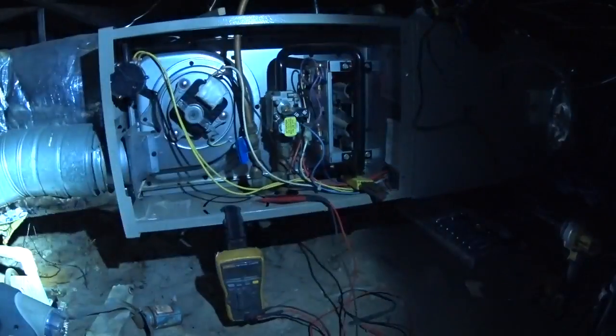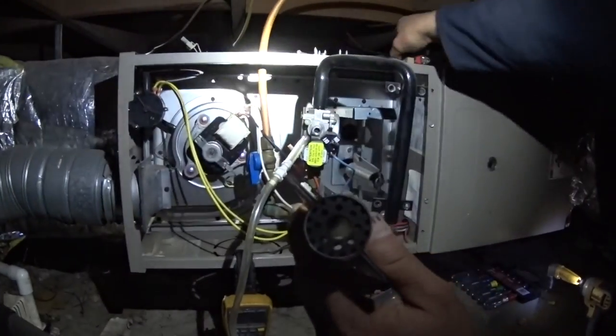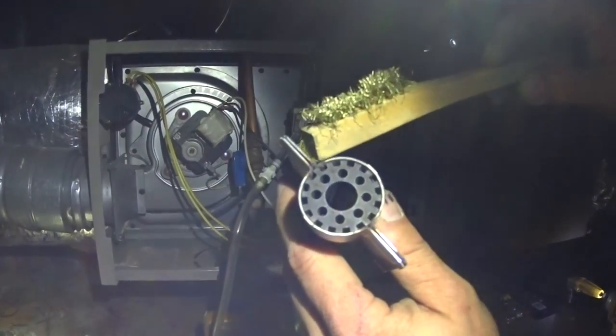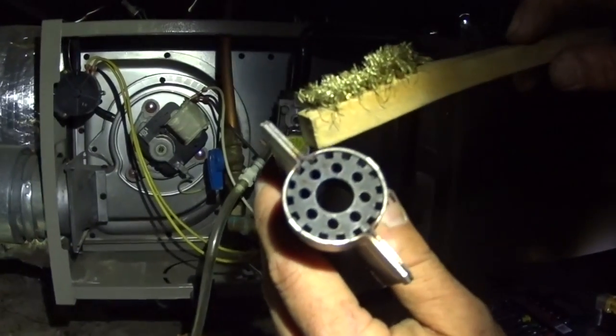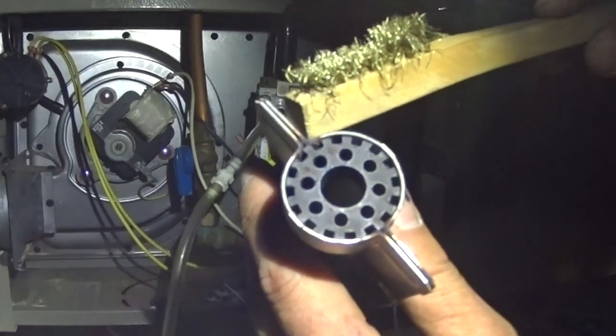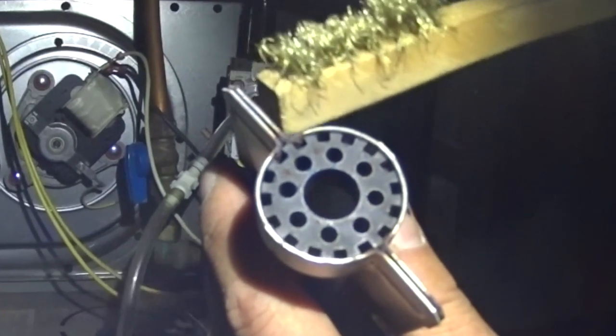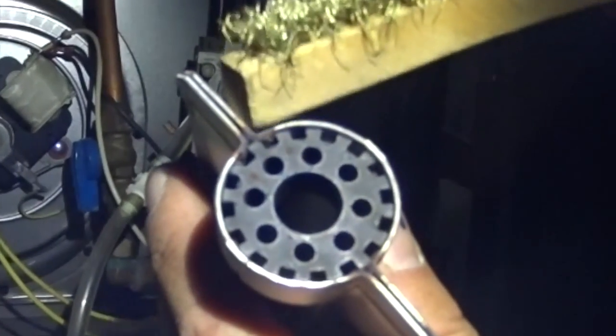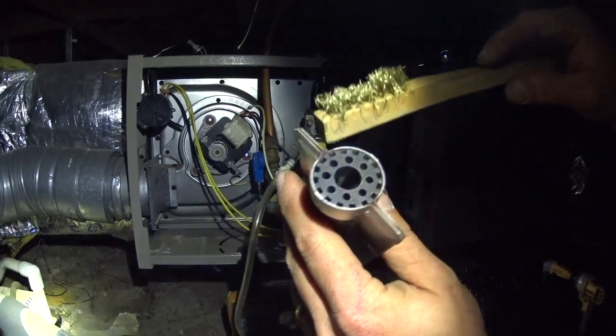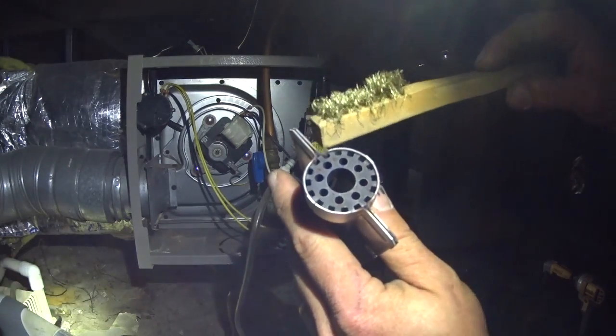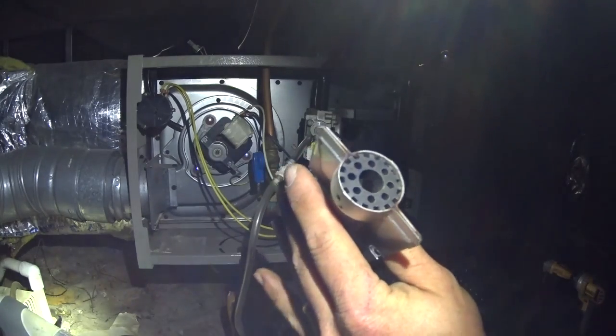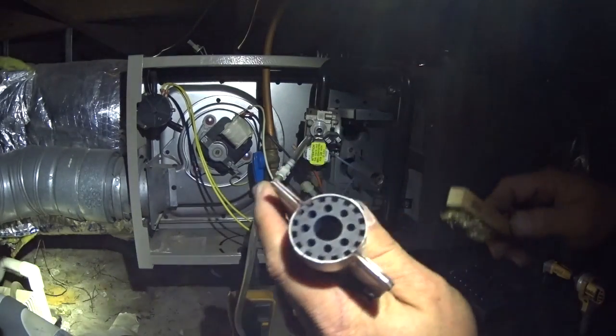So we will go ahead and give it a heating maintenance, get everything straightened out. If you look right there, the corner of the burner tube where it goes into the passover slot is full of rust. So it's going to impede how well the gas carries over between the two burners. I'll go ahead and get those cleaned up.